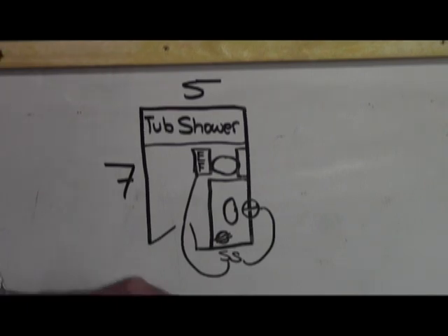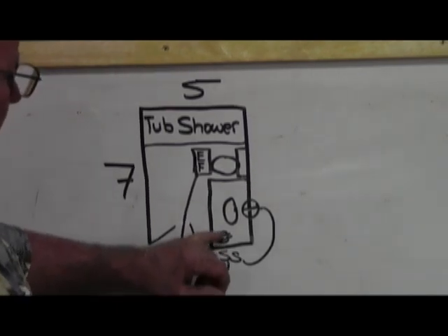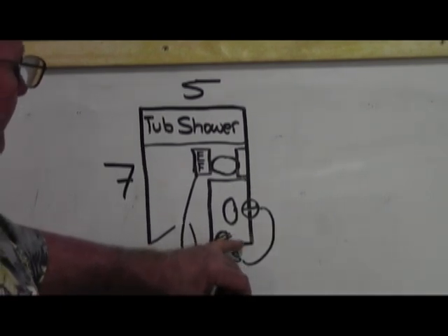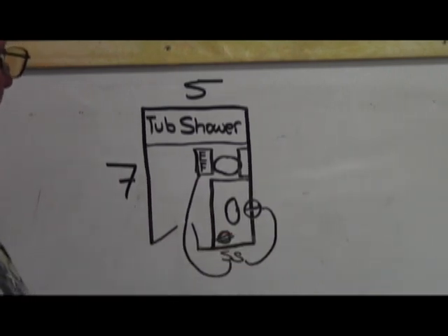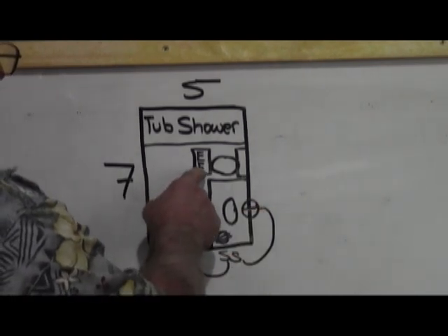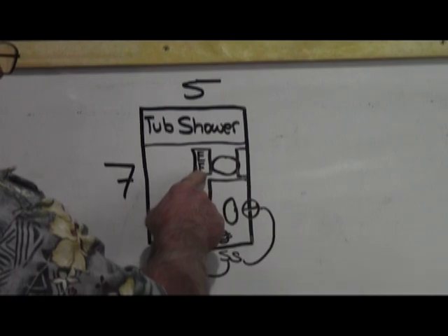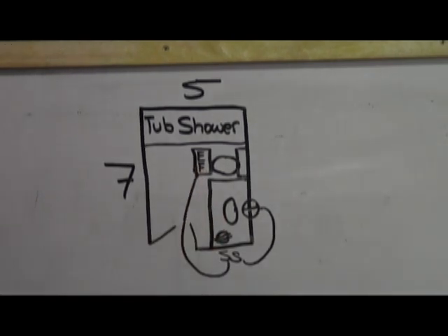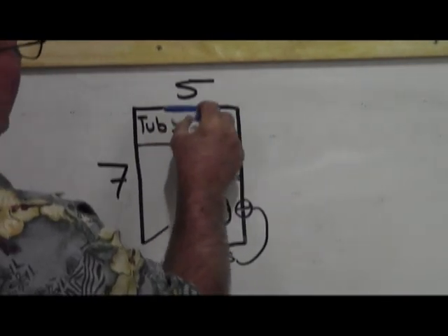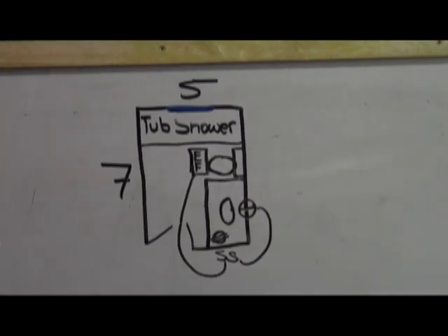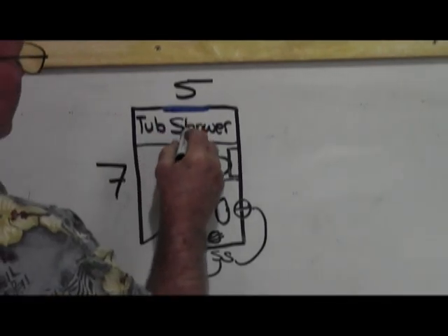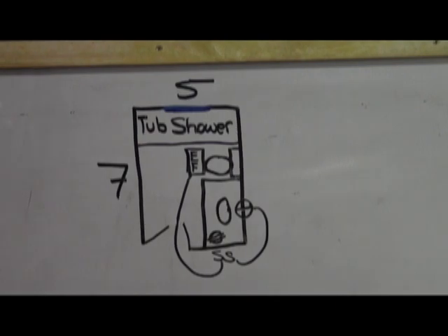Well, the first thing you want is 2 switches. They're on the inside here, but I couldn't draw it like that. And then you want a service outlet, of course GFI protected, and you have a switch to a light, and then you have to have an exhaust fan. The only exception to an exhaust fan is if you have a window, and even then I strongly recommend against relying on the window to get rid of the steam, because it just don't work. So that's your first scenario.